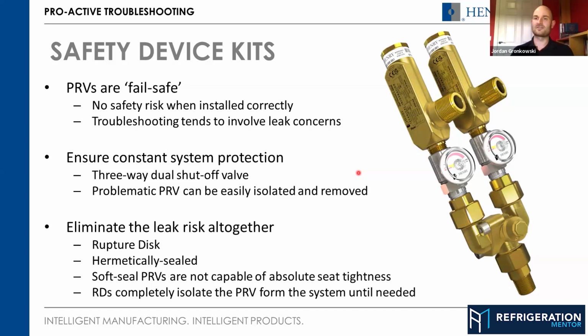Again, something else that's kind of not a misconception, it's just something that's not really publicized a lot, is that PRVs are so sensitive. They're designed to be sensitive. That is the point, because a normal non-relief valve will open slowly with pressure and then close slowly again. PRVs are designed in such a way that a small increase in pressure will lift the valve very suddenly, and that's all down to the internal aerodynamics. But once it comes back down again, because of this sudden opening, you often get a sudden closing again, and the force of that reclosing action can affect the set point.